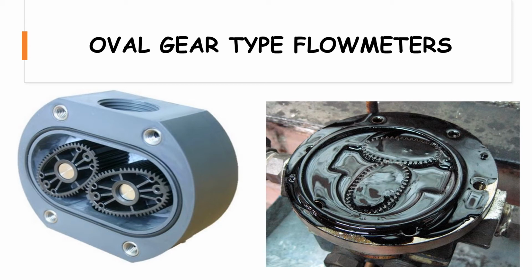The capillary action of the metered fluid forms a liquid seal. Each pocket holds a precise and known volume of fluid, so counting the pocket frequency gives a measurement of the volumetric flow rate. This is typically achieved by embedding magnets in the rotors, which then actuate a reed switch or provide a pulse output as they rotate.